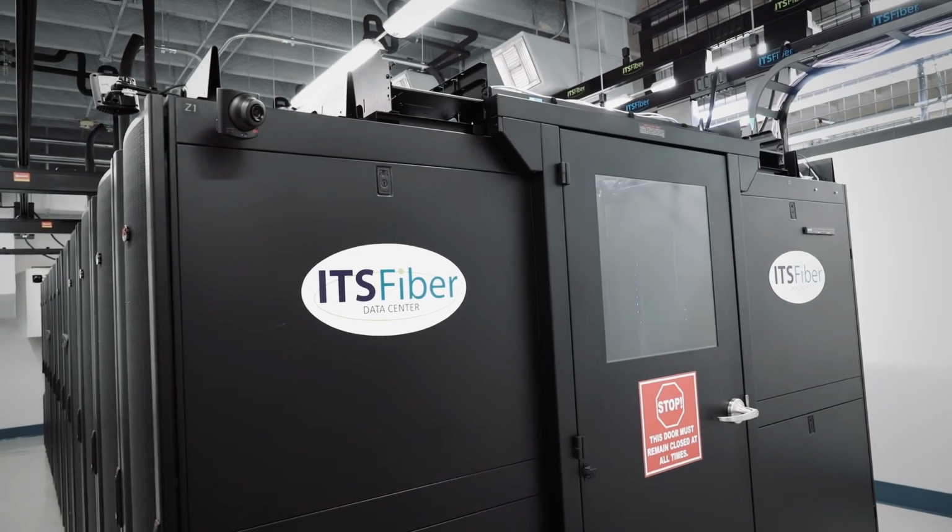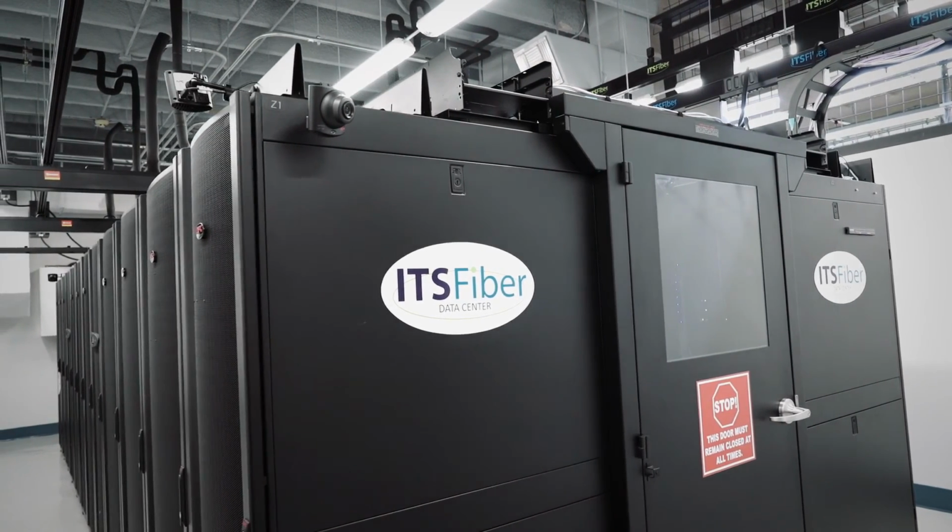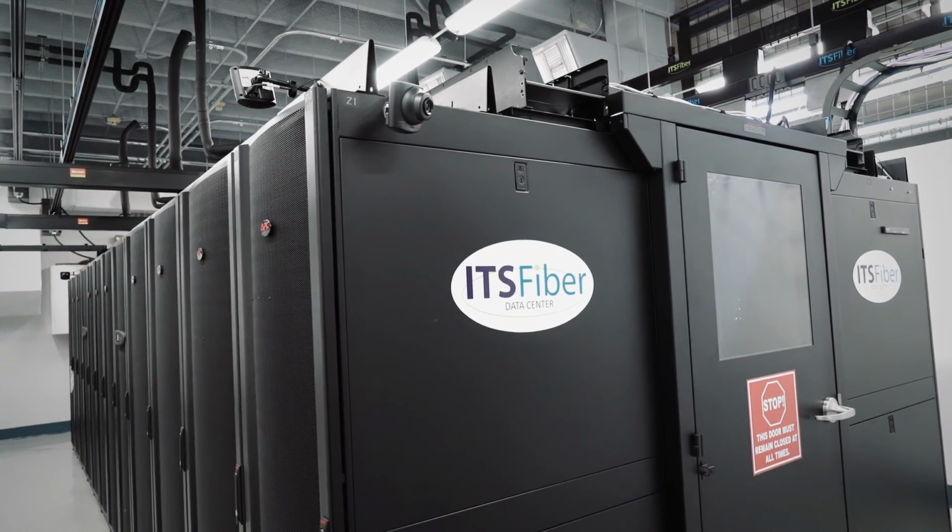This design is modular, and it allows you to grow and scale out if you have the room in your facility. With containing the hot air in the aisle, it allows us to keep the ambient room temperature at about 75, 76 degrees, which is more comfortable and more efficient on our energy.